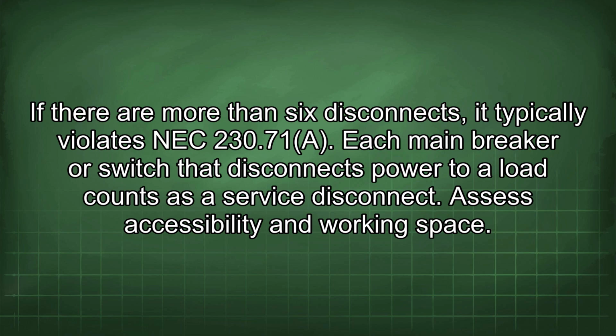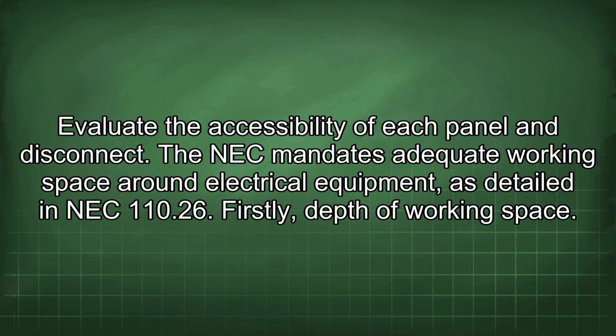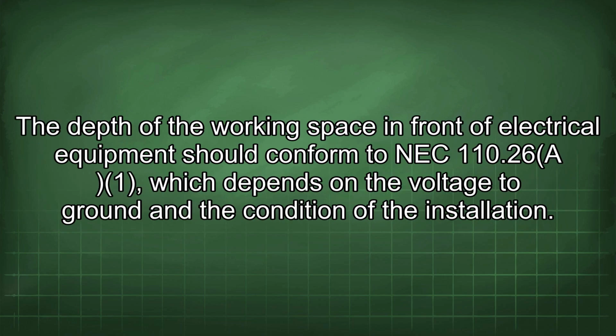Assess accessibility and working space. Evaluate the accessibility of each panel and disconnect. The NEC mandates adequate working space around electrical equipment as detailed in NEC 110.26. Firstly, depth of working space. The depth of the working space in front of electrical equipment should conform to NEC 110.26a, which depends on the voltage to ground and the condition of the installation.